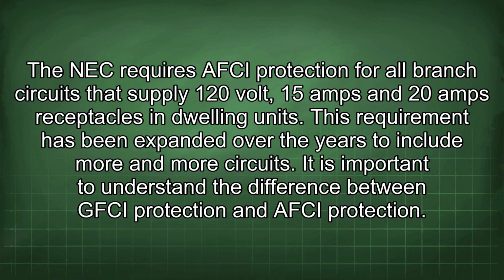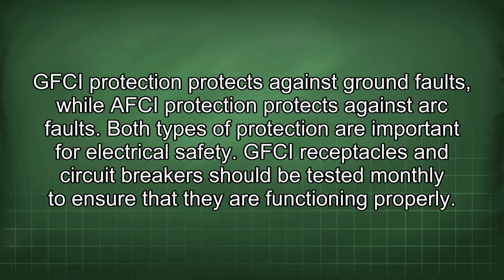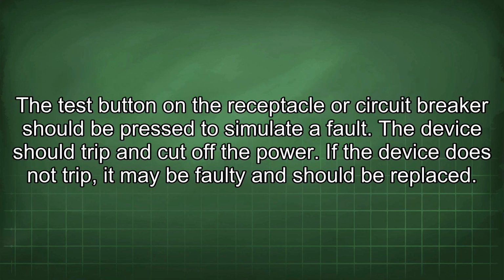It is important to understand the difference between GFCI protection and AFCI protection. GFCI protection protects against ground faults, while AFCI protection protects against arc faults. Both types of protection are important for electrical safety. GFCI receptacles and circuit breakers should be tested monthly to ensure that they are functioning properly. The test button on the receptacle or circuit breaker should be pressed to simulate a fault. The device should trip and cut off the power. If the device does not trip, it may be faulty and should be replaced.